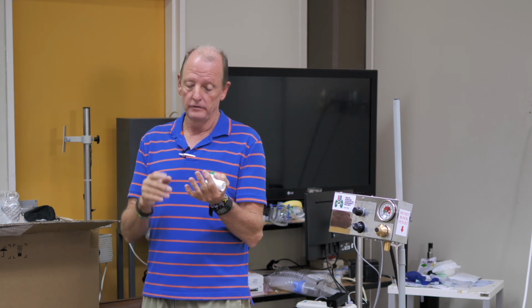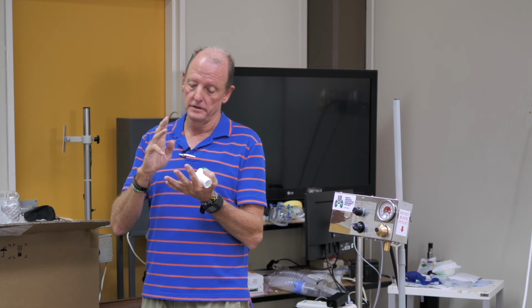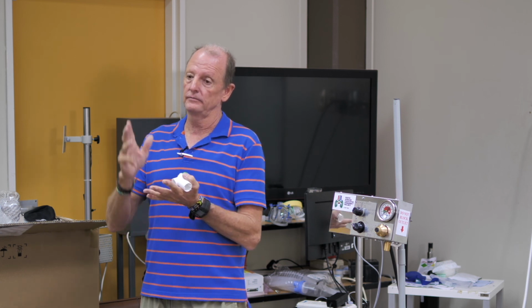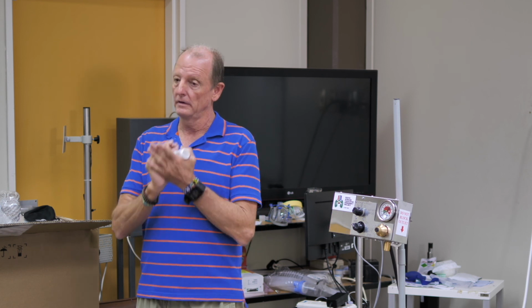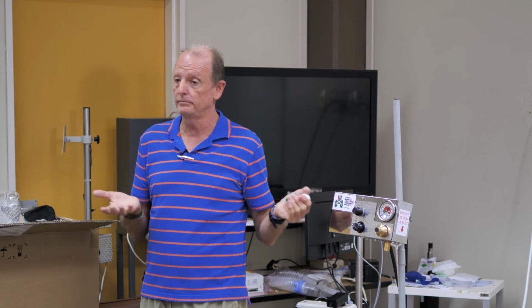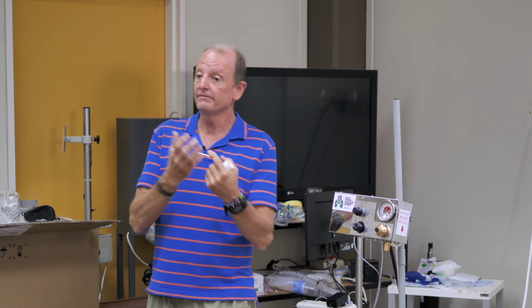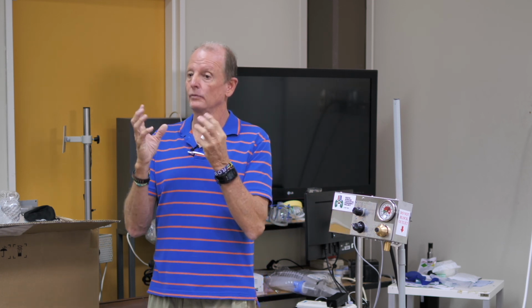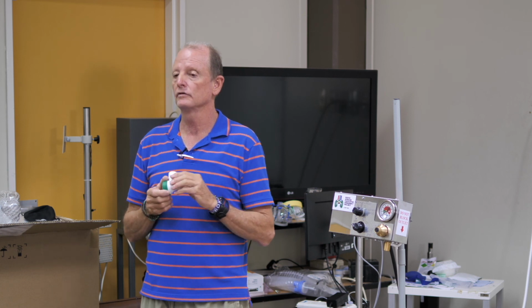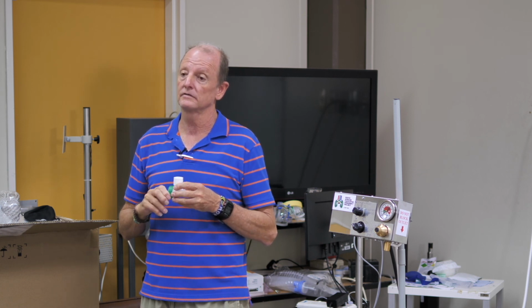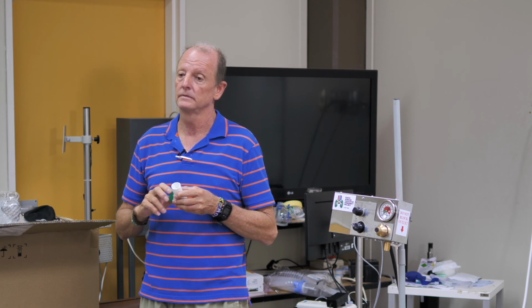Every 2 years is the big major service. That's like a normal one. You've got sintered filters, shuttle valves, diaphragms, you name it, all the O-rings; they should all be replaced. Obviously, with oxygen and air at high flows through the regulator, you get water moisture, so it can create problems. So yeah, every 2 years. There is a yearly inspection that's got to be done by us as well.